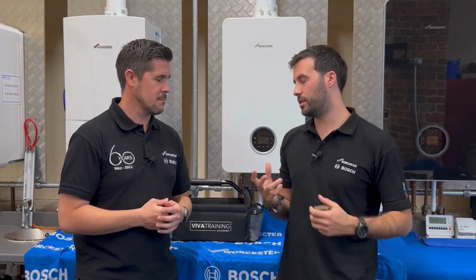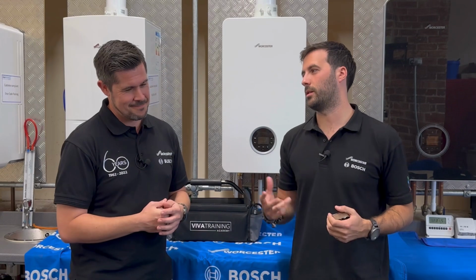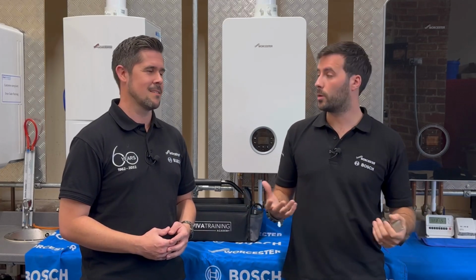Good question. There are two potential reasons. Plates can get blocked because there are two sides to a plate heat exchanger. You've got the water side, where your domestic water goes through, and if you live in a particularly hard water area, unless you put scale protection on there, it will scale up at some point. Those in really hard water areas almost expect that. But you can do things to protect it, like scale reducers or softeners.